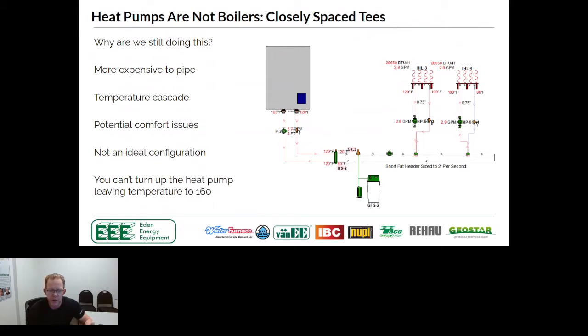But what I would say to you is I would move away from this mentality, look at a short fat header. It will make sure that every single zone is getting the exact same temperature. It will make sure that if we want that heat pump running at 120 for radiant floor systems, we can set it to 120. We're not setting it to 140 so that the first set of tees is getting a better temperature than the last set of tees.